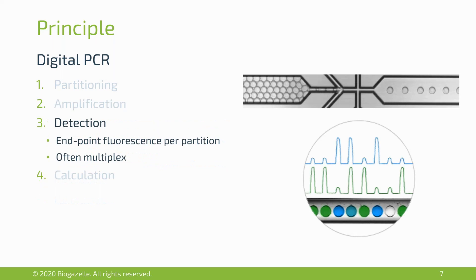The third step is detection. Unlike qPCR with real-time detection, here every chamber or droplet must be screened. In the example from the Bio-Rad instrument, the droplets are fed into a channel and a laser reads out each individual droplet, screening the different channels for the presence of amplification products across the different multiplex reactions.